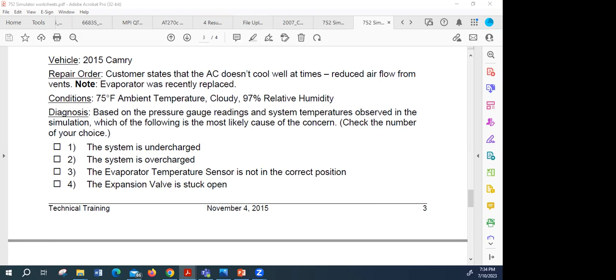What if the expansion valve is stuck open? What would happen? It doesn't get frozen. What would the pressures and temperatures be? The pressures would almost be equal. If it was stuck wide open, it wouldn't make a restriction, so it couldn't build a high or draw a low. So that's correct, but that's not what we have, we've got a low that's too low.